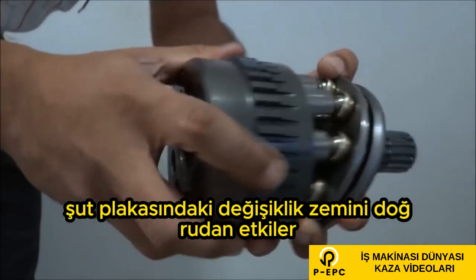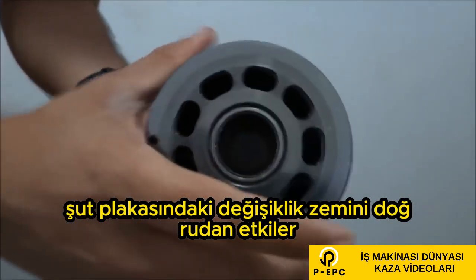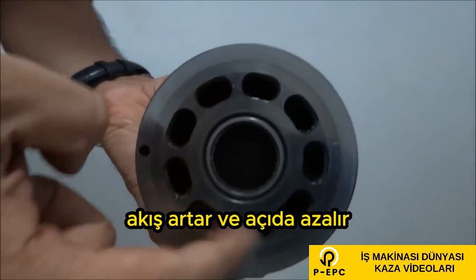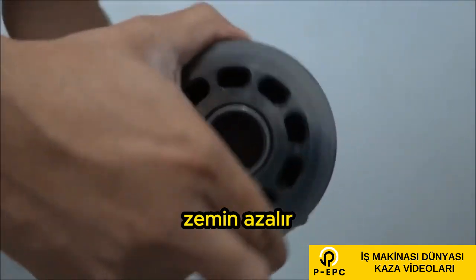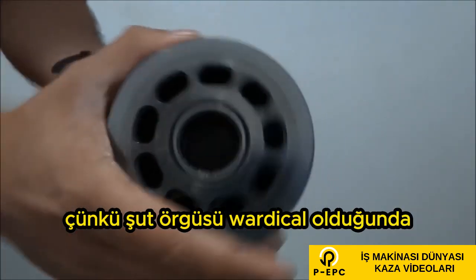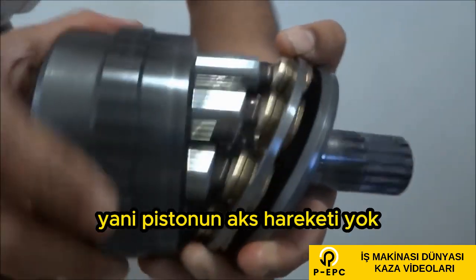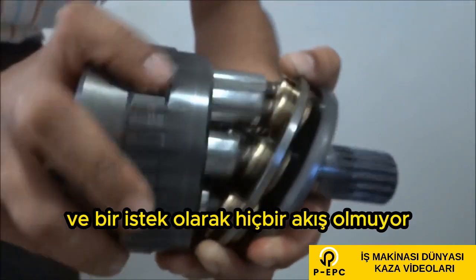The change in swash plate angle directly affects the flow. When increasing the angle, flow increases, and decreasing the angle, flow decreases, because when the swash plate is vertical, there is no piston movement, that is, there is no axial movement of the piston, and no flow is happening.